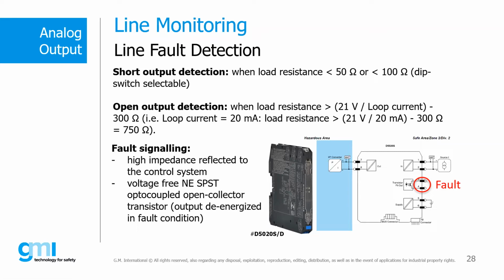This threshold can be set via an internal switch. However, as for the open circuit, it's signaled when the threshold given by the formula 21 volt divided by loop current minus 300 ohm, 750 ohm in this case, is exceeded. This threshold, as you can understand from the formula, is strongly dependent on the current that the PLC supplies to the loop. But how is this fault reported to the system?